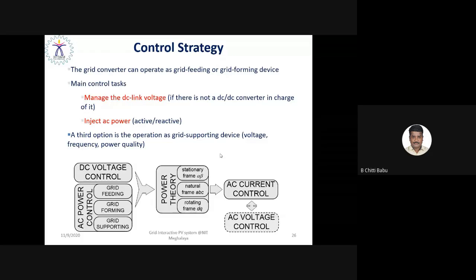Frequency must be maintained constant, and the variation should be within the acceptable limit that they specify in the Indian grid. The frequency variation should be between 49.5 and 50.2. Moreover, the voltage profile at the point of common coupling should be within the plus or minus 5% range, according to the IEEE 519/2014 standard, right? That has to be maintained with the help of AC current control as well as AC voltage control on the inverter output side, and DC voltage control on the inverter input side. So the converter has to handle both the DC parameter as well as the output AC parameter.